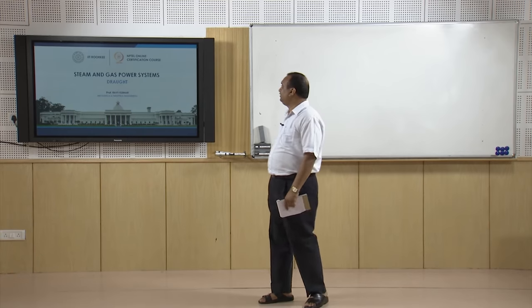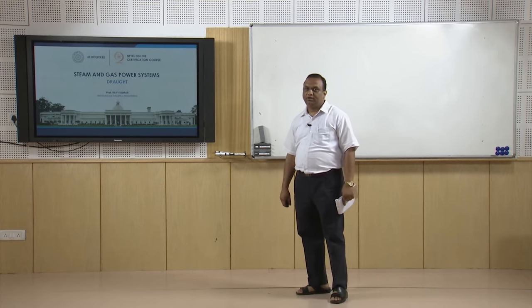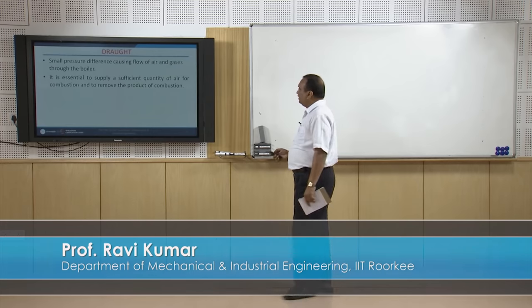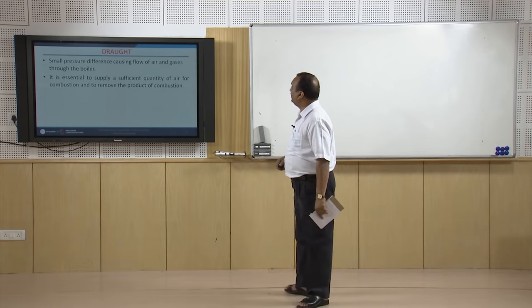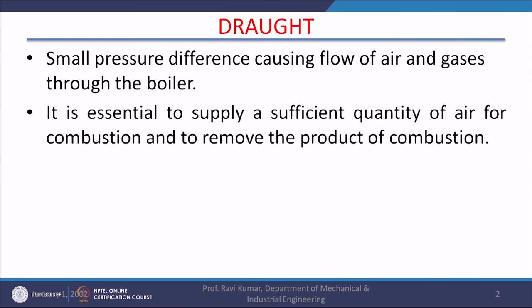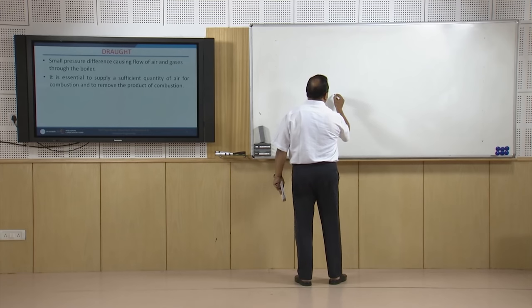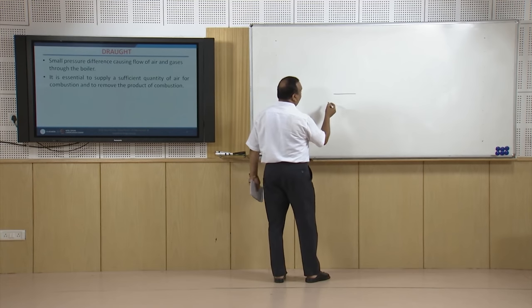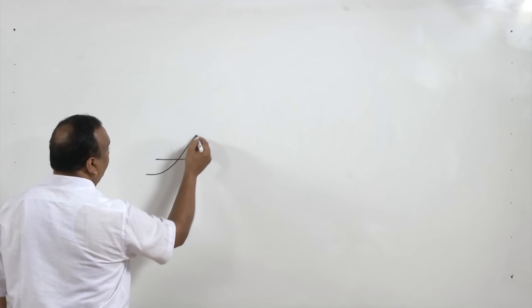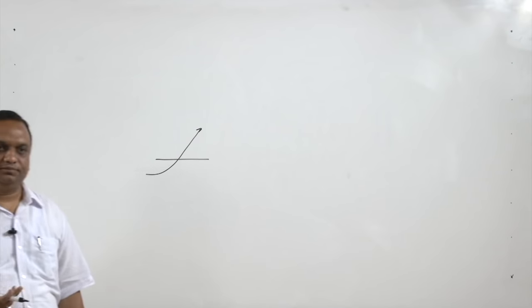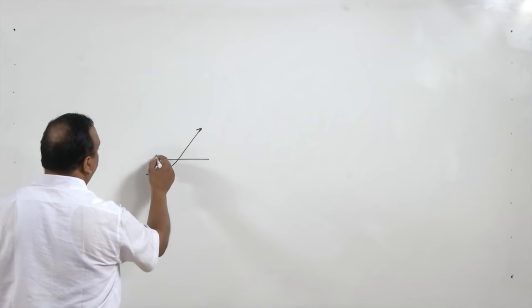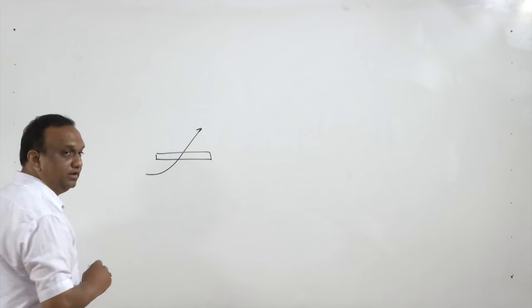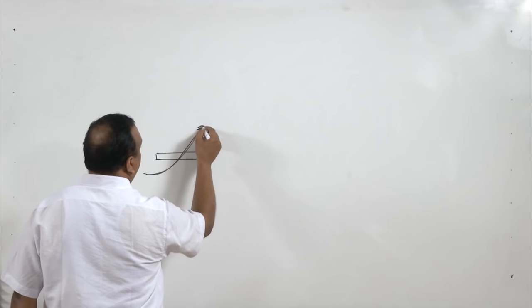Welcome to this course on Steam and Gas Power Systems. Today we will discuss draft. Draft is a small pressure difference causing flow of air and gases through the boiler. It is essential to supply sufficient quantity of air through the grate because fuel is burned there, and the designer must ensure sufficient air is available; otherwise the fuel will not burn and boiler efficiency will go down. To ensure complete combustion of fuel in the grate, air circulation must be maintained.